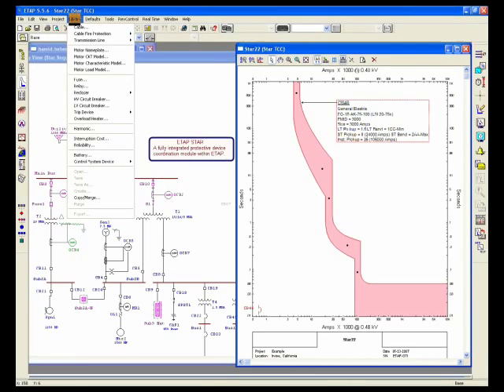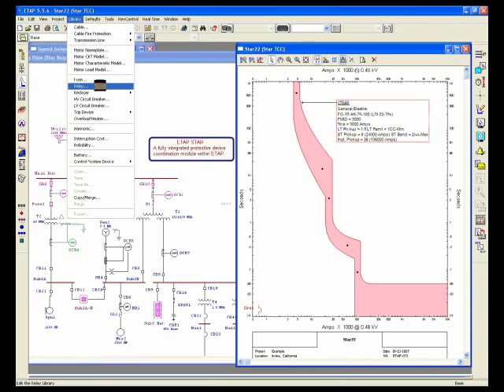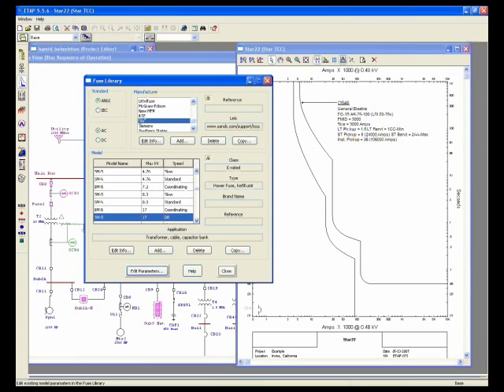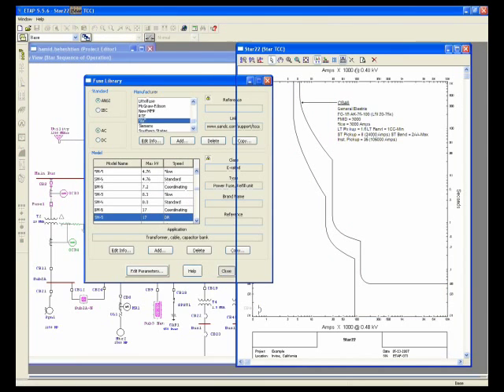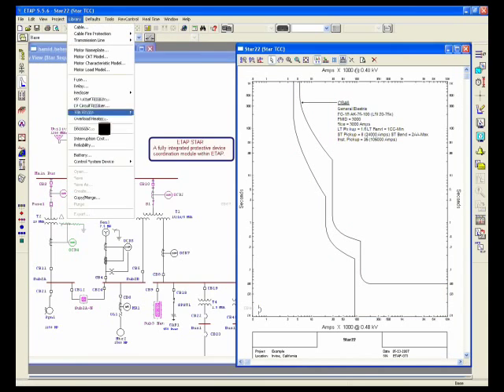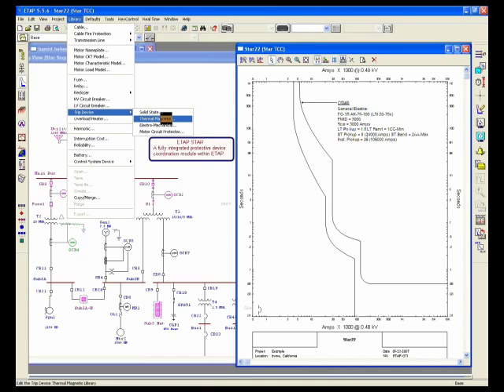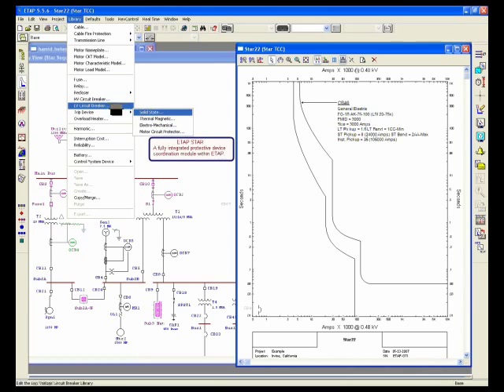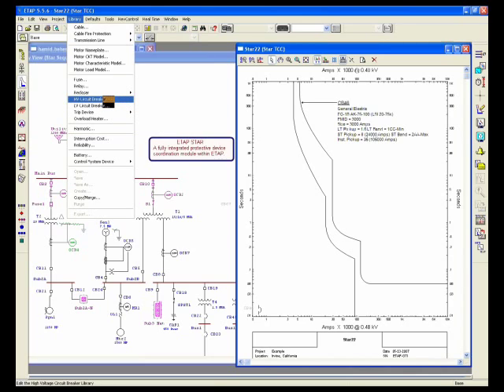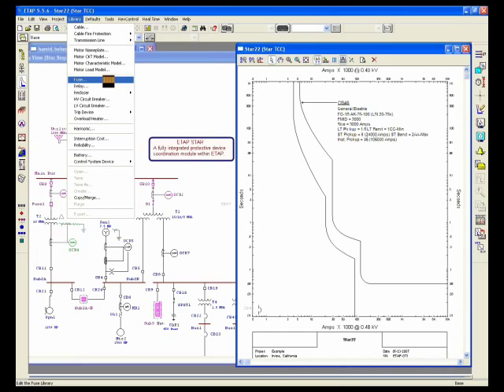By doing that, just as a quick summary, we know how to add fuse, we know how to add the low voltage breaker and how to add the trip devices. I hope it helps you to play around with these trip device libraries and the breakers, so next time if you have any new models which are not available, you can add it by yourself to the library editor. Thank you so much.